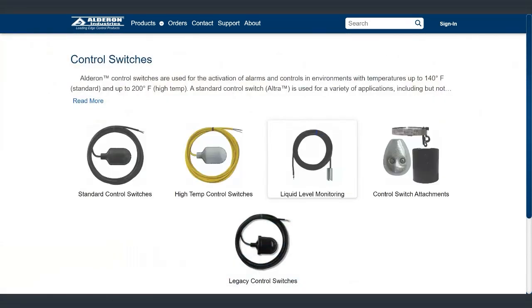Control switches, we have a few different control switches and attachments. Our new control switch is our Altra control switch. You can use this for up to 5 amps, and it's 120 or 240 rated. Bare leads, always bare leads for control switches. So you can use that to activate the contactor to turn on the motor or the pump, or for alarm situation, connected to the alarm.